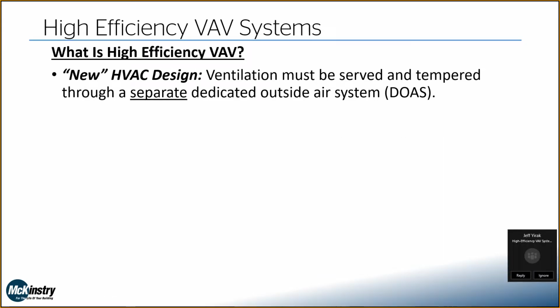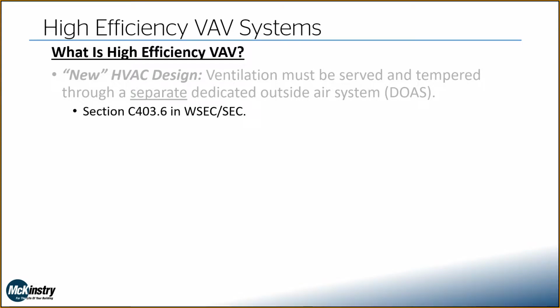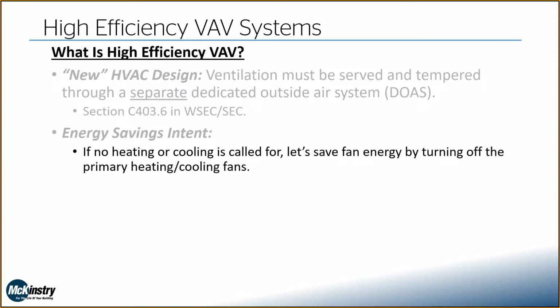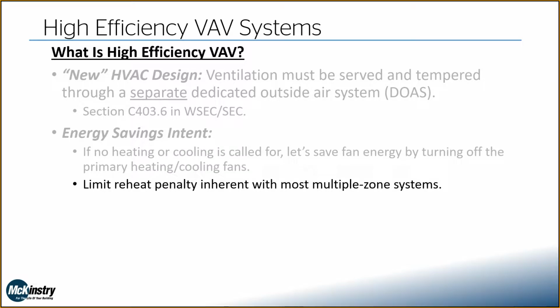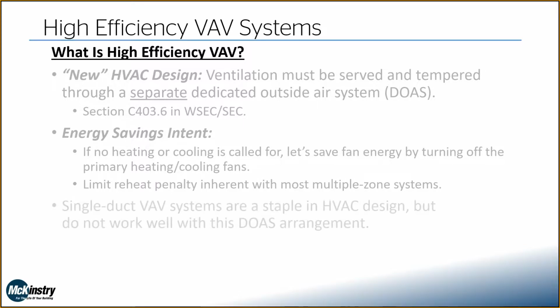So what I'm calling here the new HVAC design. What is the code requiring now? I already mentioned ventilation. We have to serve and temper that through a separate dedicated system, or a DOAS. This is section C403.6 in both of the codes. And the intent here, the reason they want us to do this, is if you have a system that's not calling for heating, not calling for cooling, well, we can save some fan energy by turning off those primary heating and cooling fans. Just let the ventilation fan run. We can also limit the reheat penalty that's going to be inherent with most multiple zone type systems. So a standard VAV system, for example, has some inherent reheat penalty that has to be paid.